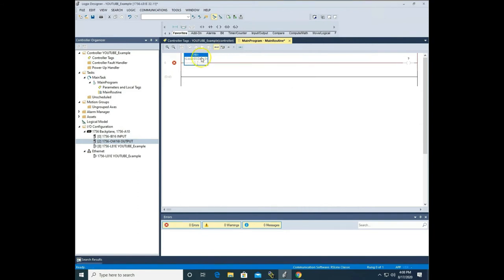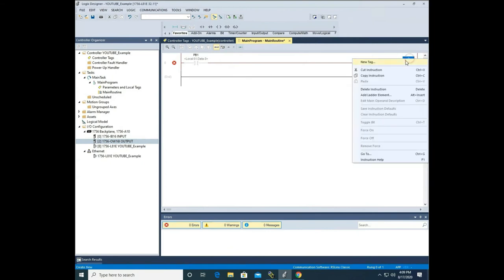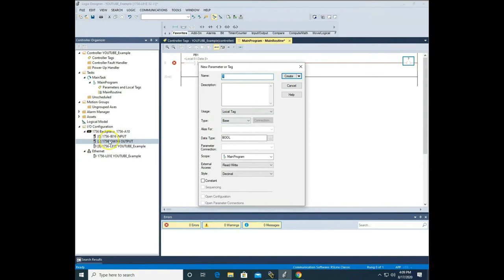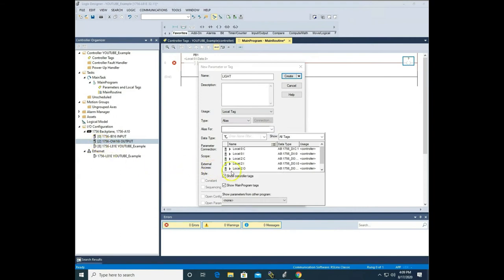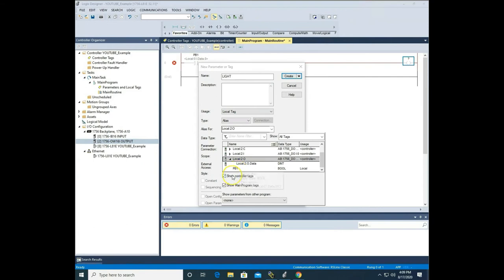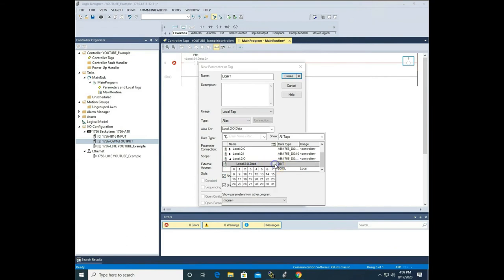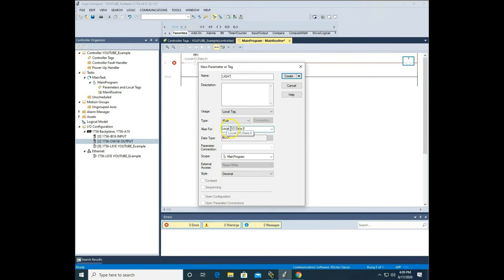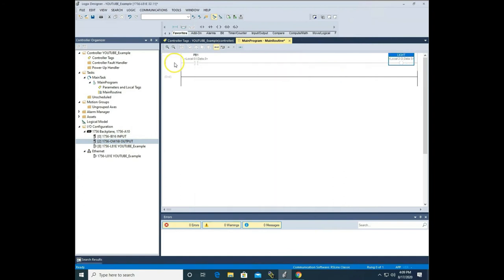We still have a red X because we don't have a tag on our output yet. I want to turn on a light on channel 0 of the output card, so I'll call this 'light.' Go down to type — it's going to be an alias because I want to turn on a physical output. My output is in slot 2, so I go to local 2 output. Stay away from C and I — just go to local 2 output data, hit the down arrow and select 0. Now we've got address local 2 output data 0. Hit create — notice the red X went away. We just created our first program.